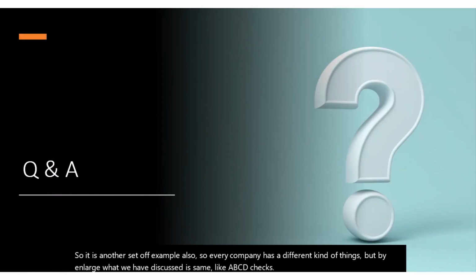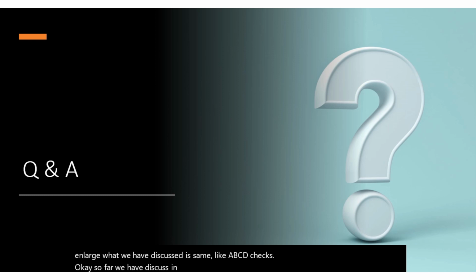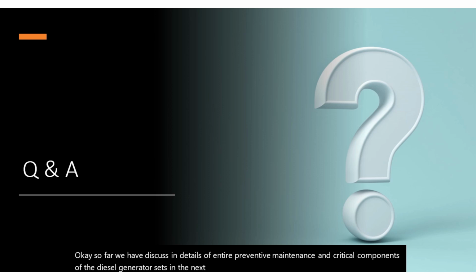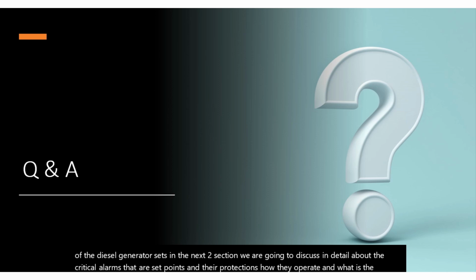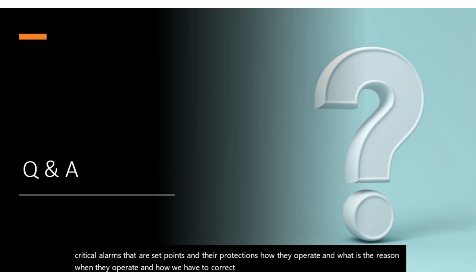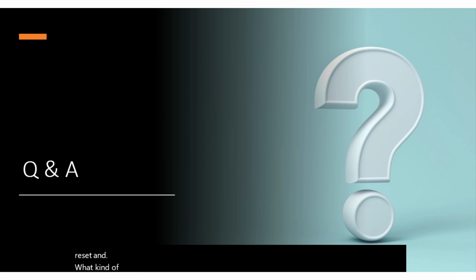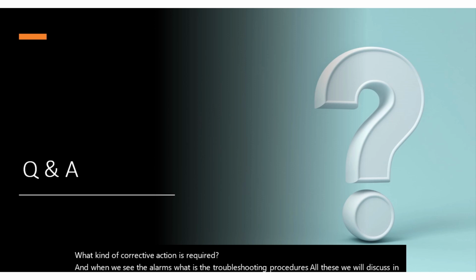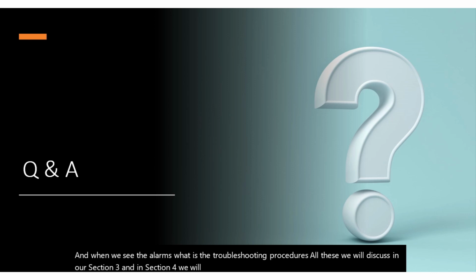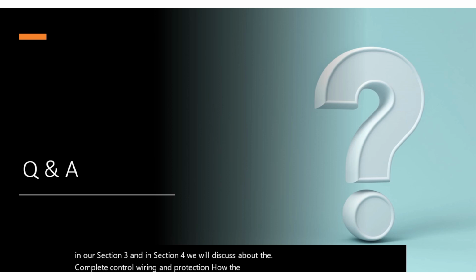Okay, so far we have discussed in detail the entire preventive maintenance and critical components of the diesel generator sets. In the next 2 sections we are going to discuss in detail the critical alarms, their set points and their protections, how they operate and the reason when they operate, and how we have to correct them, how we have to acknowledge, reset, and what kind of corrective action is required. And when we see the alarms, what the troubleshooting procedures are. All this we will discuss in section 3, and in section 4 we will discuss the complete control wiring and protection, how the relay operates and what the GCU connection is, and so on. We are going to discuss that in our last section.